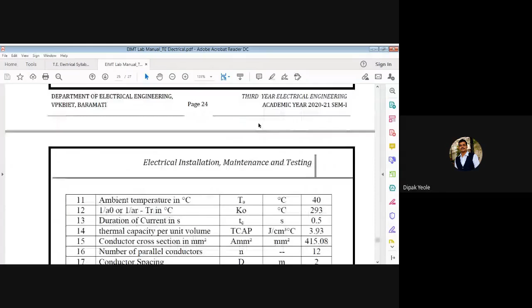What is the formula? Obviously the size is in millimeter square. So I have to use the formula: A = I divided by the square root of [(TCAP × 10⁻⁴ divided by (tc × αr × ρr)) × ln((K0 + Tm) divided by (K0 + Ta))]. These notations I am using, and I am taking the values from the given data. You can see over here, TCAP is the thermal capacity per unit volume. I have to put all these quantities together, and after that I will find the value of the size of earthing conductor, which is 415.08.